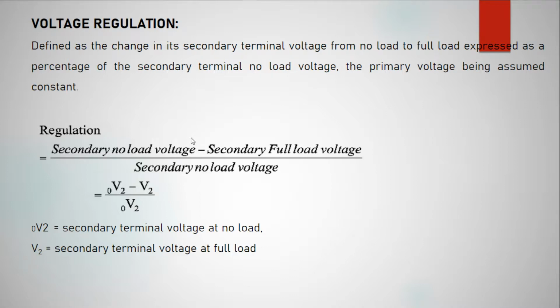Next, voltage regulation. It is defined as the change in secondary terminal voltage from no load to full load, expressed as a percentage of the secondary terminal voltage at no load, where the primary voltage is assumed constant. You can see in the formula: secondary no load voltage minus secondary full load voltage, divided by secondary no load voltage. So when there is no load, what is the secondary terminal voltage? When there is full load, what is the secondary terminal voltage? That is called the voltage regulation of a transformer.